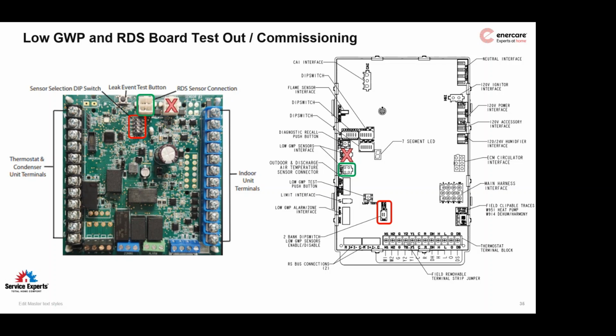In heating, you're going to follow the exact same sequence. So we're going to provide a heating demand from the thermostat and allow the furnace or heat pump or electric heat strips in an air handler to run and basically stabilize. The fan gets started, it's starting to deliver heat. You've established a solid call for heat. And the process is still exactly the same. Go ahead and push that test button one more time, give it a little push, and then release it. What'll happen is the burner should shut off after a short period of time. The electric heat strip should shut off, or the heat pump should shut off, depending on what heat function is running.